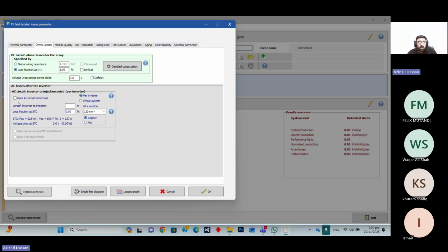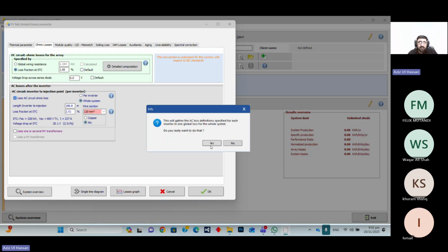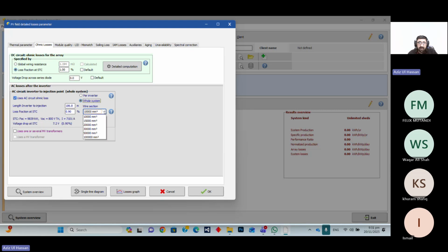So in inverter cases, the AC loss allowed is 1 to 1.5%, so we should put 1.5%. Okay. So you just have to select the aluminum cable and check the whole system, because we are doing the whole system. We have to allow the 1.5% loss. So now the other option is available.